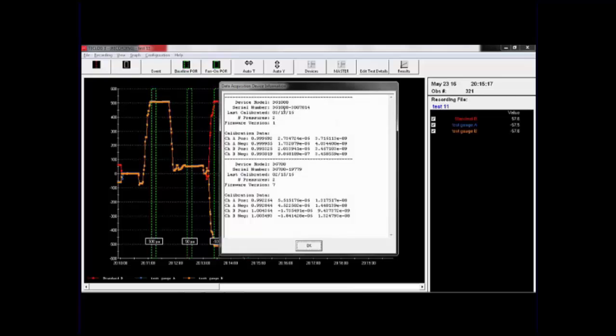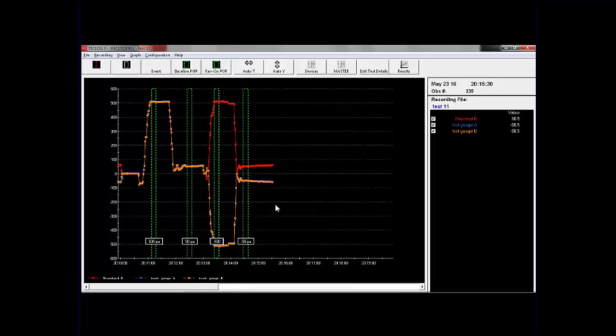Then I'm going to go up to recording. Oh, one other thing I'll show you before I do that is if we go up to view, we can choose DAB DG information, so view, DAB data acquisition box, DG information, and that'll show our serial numbers and our last calibration dates. So then that way we have documentation that our standard gauge was calibrated within the last 6 months. So that's great documentation for that. You've got proof, and this becomes your document.